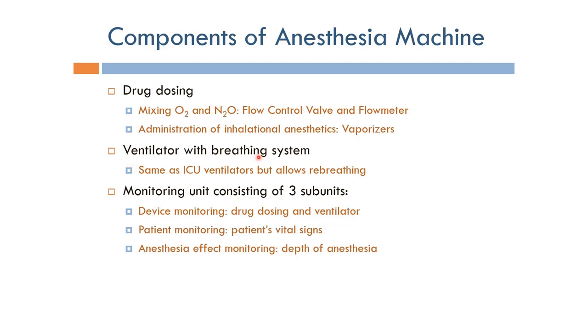The second component is the ventilator with breathing system. This is basically the same as intensive care unit ventilators, with the only difference being that it allows rebreathing of the expired air.